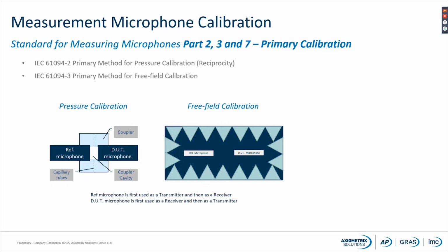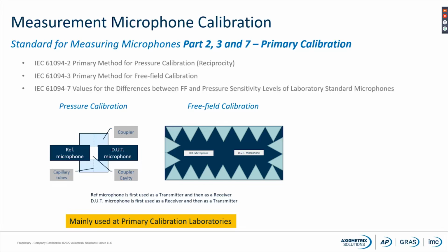In this way we are able to measure very, very precisely the sensitivity of the microphone. And as mentioned, reciprocity measurements is mainly used in primary laboratories.